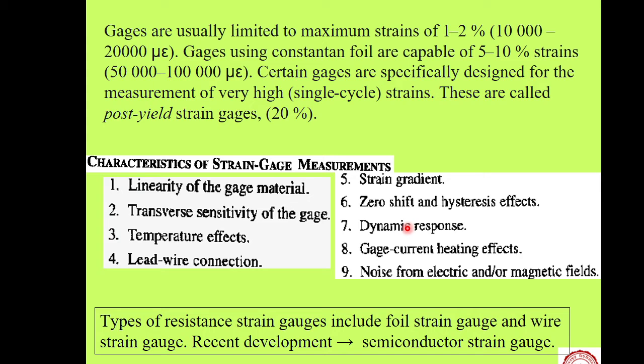Strain gauge does not have a very good dynamic response, so they are not meant for dynamic application. In such applications, we have to use piezo crystal based strain gauges. In the previous slide we had some discussion of piezo crystal based strain gauge. Those are special purpose.